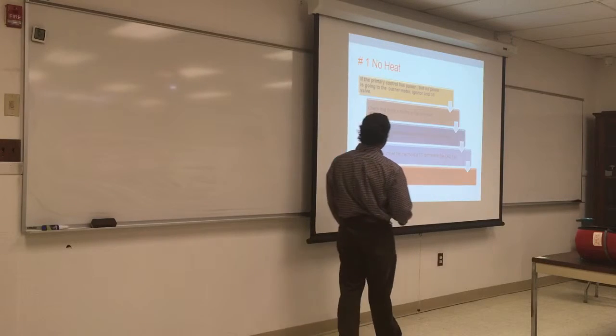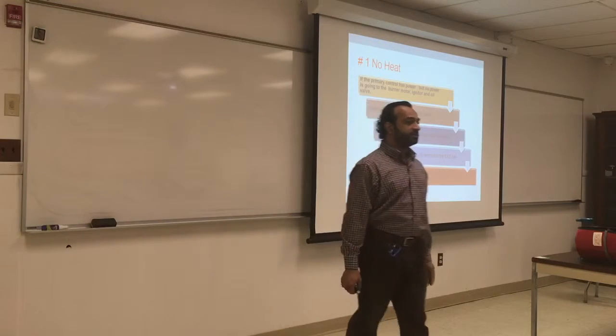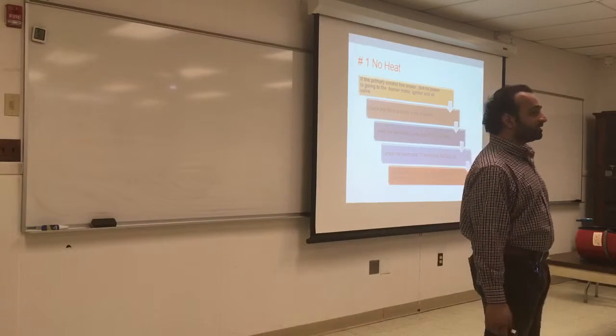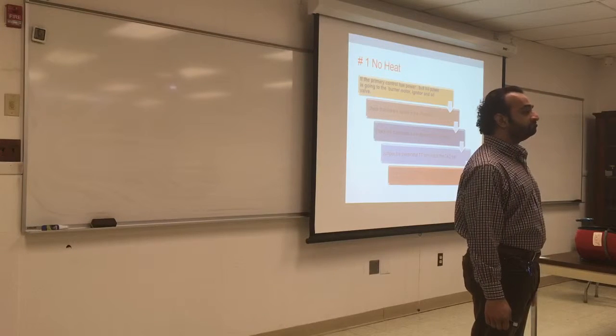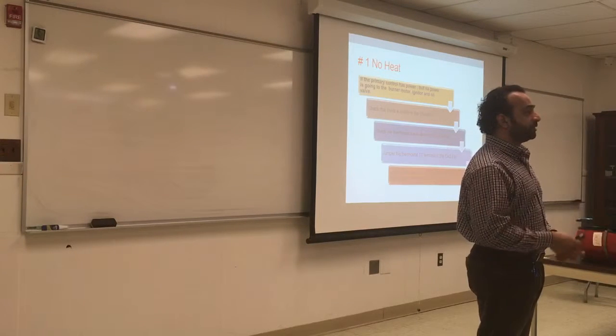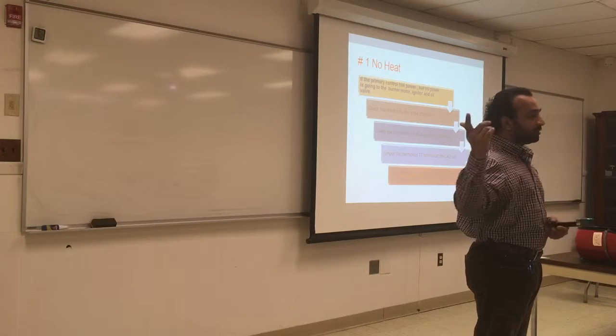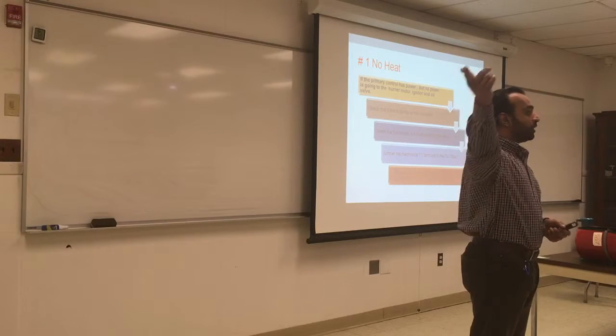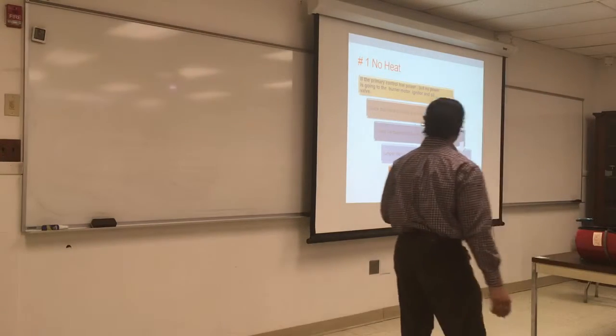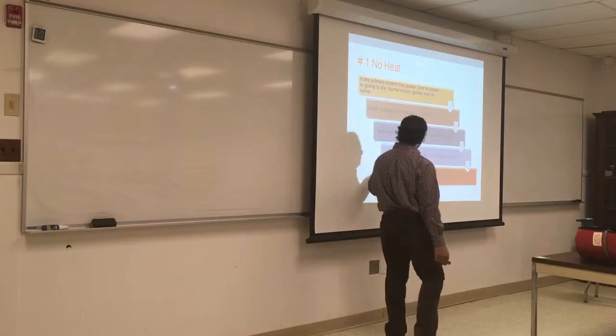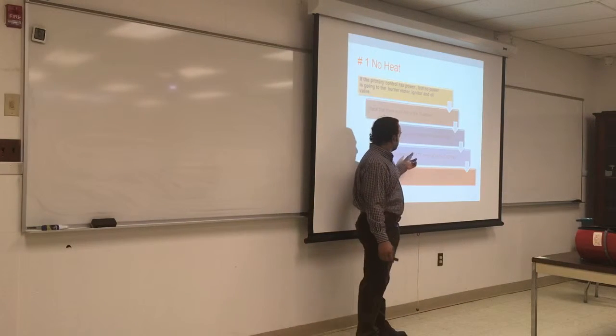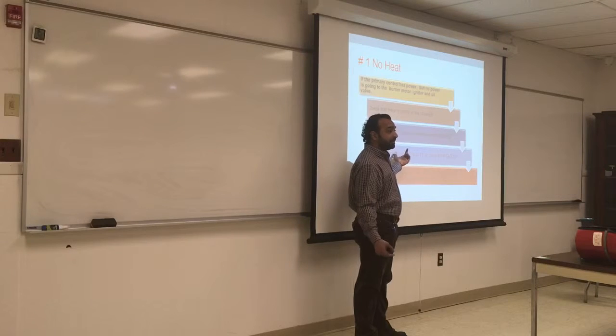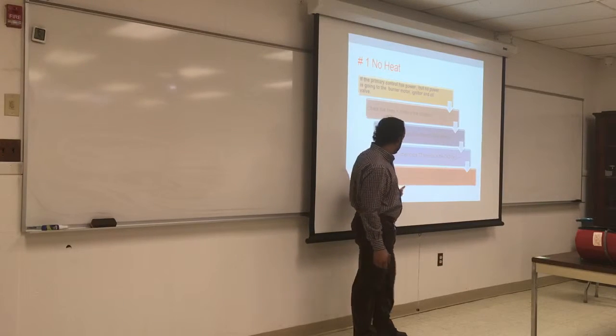Next step, check that the thermostat is set above the room temperature. It's set above the room temperature. Okay, let's go and jump on the thermostat and see what happens. If it works, something is wrong with the thermostat or the wiring from the thermostat all the way to the primary. So we jump it, and if it works, I mean it's the thermostat. If not, we can go further.